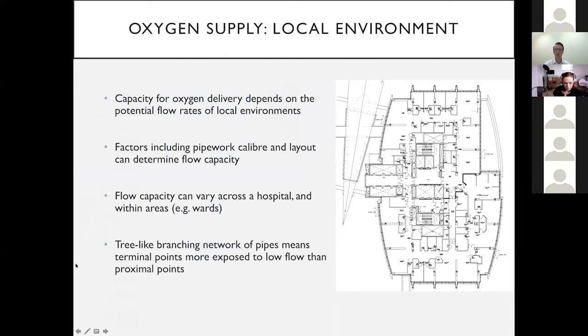But it's not just the overall oxygen flow capacity that determines whether an area can support CPAP and how many CPAP devices it can support, because the local flow area capacity is determined by factors including the pipe layout and the pipe caliber. So to understand where best to place CPAP, you need to understand the engineering architecture. Specifically, the branching network of pipes means that terminal points in the pipe network will be more exposed to low flow than proximal points.